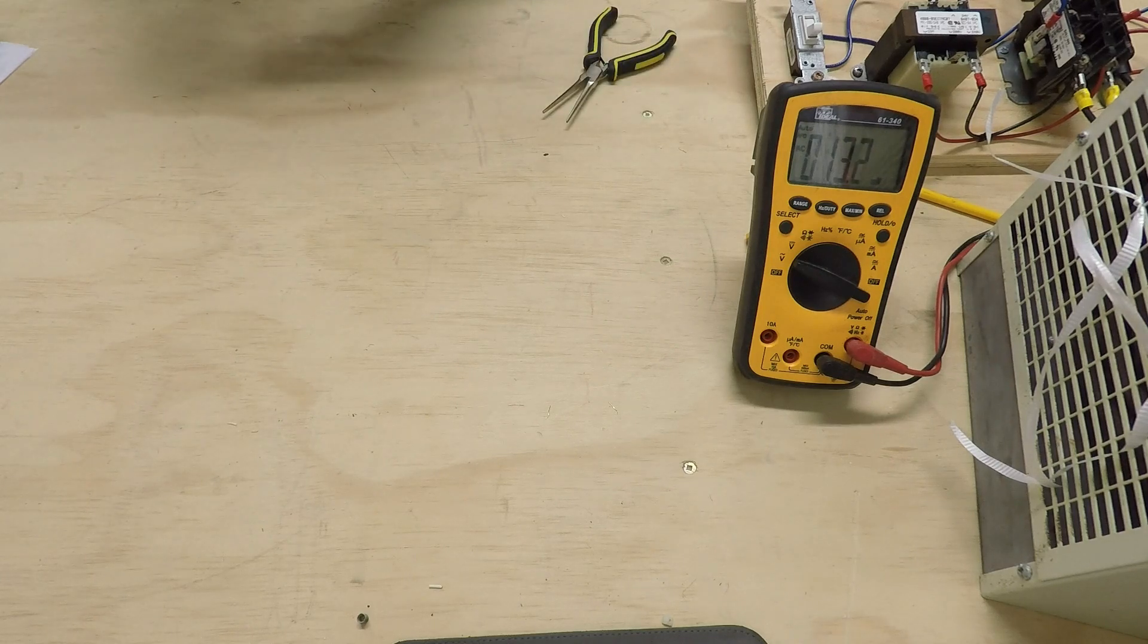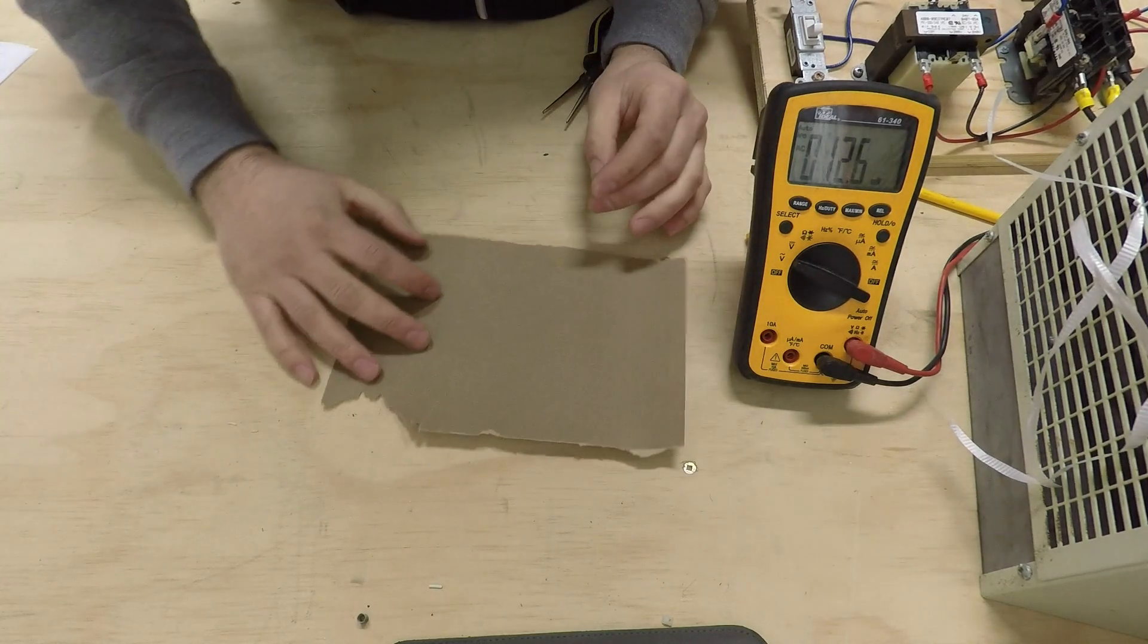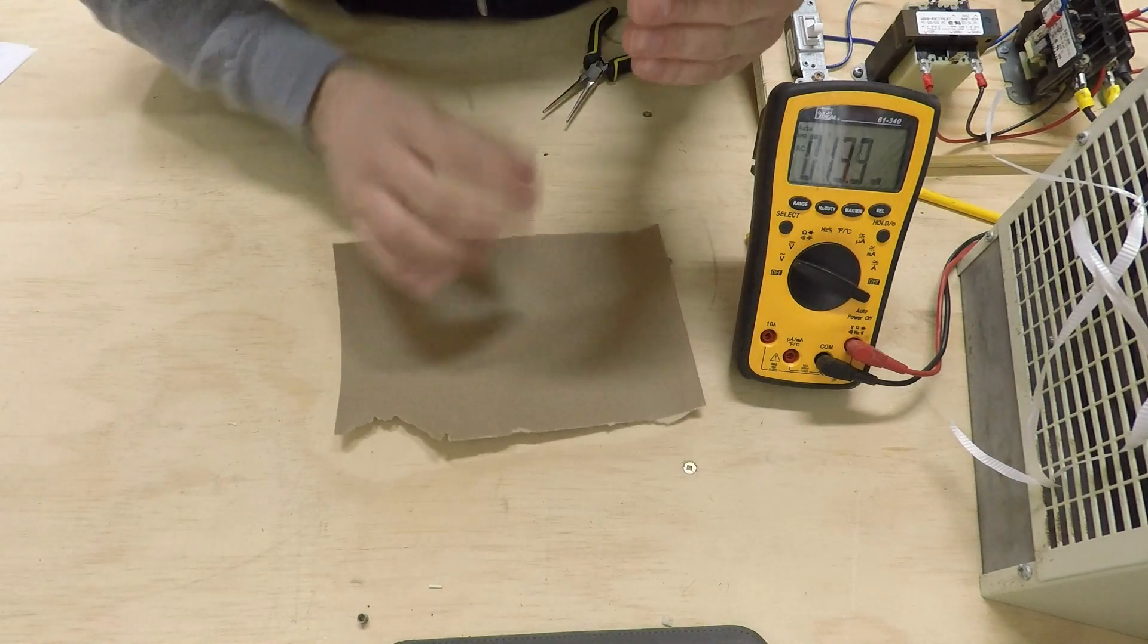And what you can do now is you take some sandpaper, and I'll show you the contact up close. If you look closely at it, hopefully it shows up, you can see it's kind of charred, burnt. It looks like there's probably some pitting on it also.